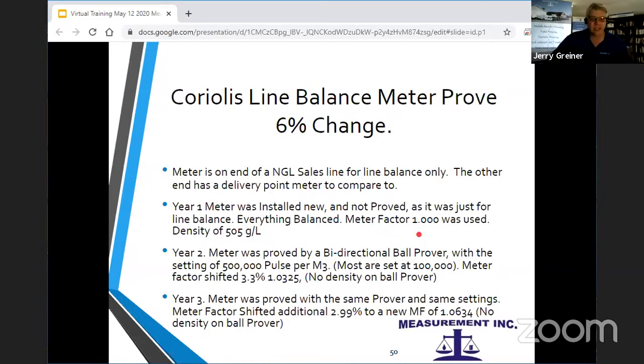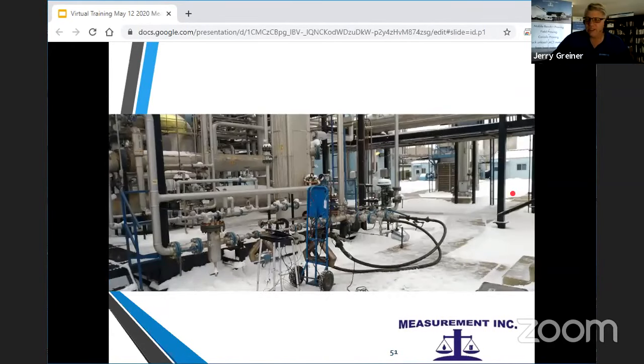The second year they came to prove it again. They used the same prover, the same settings, the same bidirectional ball prover. It shifted another just about 3% to give a new meter factor of about 1.06. And once they entered that new meter factor, their line balance was out of balance because there was so much differential. It was 6% out basically, and on a line balance meter, once they're over 5%, it triggers alarms nonstop.